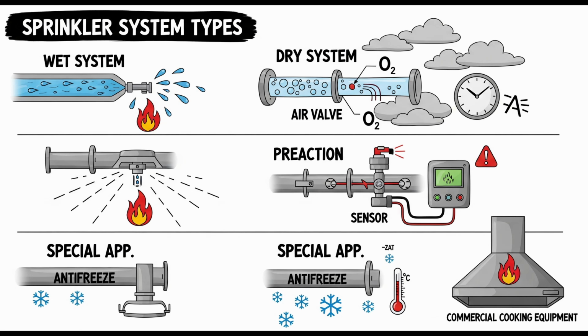Four options again. Okay. Option 1. A maximum system volume of 500 gallons is permitted without requiring any specific water delivery time calculation or test, similar to the small dry pipe allowance. Okay, volume-based. Option 2. The system must be designed to deliver water to a test connection in no more than 60 seconds. This test is performed starting at normal air pressure, if used for supervision, and with both the detection system activated and the inspection test connection fully open simultaneously. So you have to simulate both conditions happening at once for the test. Right. Option 3. The size can be based on hydraulic calculations for water delivery, similar to the dry pipe calculation method, assuming simultaneous detection system activation and sprinkler operation.